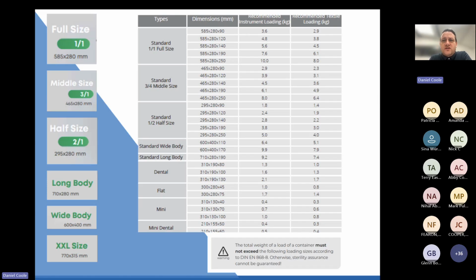There's also restrictions around loading. So here you can see in this table on the right that there's a weight guidance that you should not exceed, obviously from a health and safety perspective for your colleagues who are handling these on a day-to-day basis. So for instance, if we take one of the more popular sizes, you're looking at something like 585 by 280 by 190 there. That's just over 7.5 kilos. So it's not actually particularly heavy when you think about loading up lots of surgical instruments, with some sets having upwards of 100 instruments or so in them. So of course, that's a big consideration.